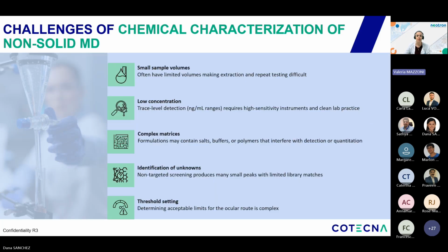In particular, liquid medical devices present some of the most demanding challenges for extractables and leachables evaluation. First, we often work with very small sample volumes, which limits the amount of material available for analysis and requires highly sensitive, low-background methods. At the same time, these products typically contain extremely low concentration leachables, pushing our analytical systems to their detection limits and increasing the need for clean workflows and robust quantification strategies.